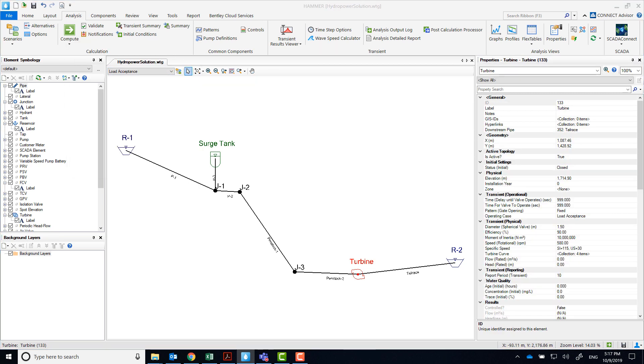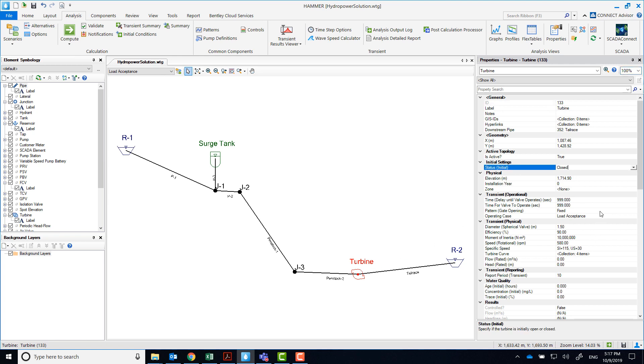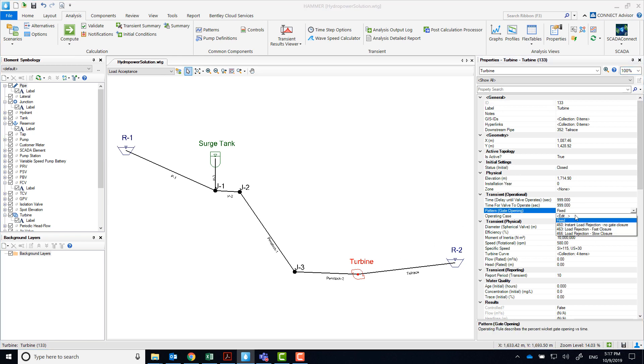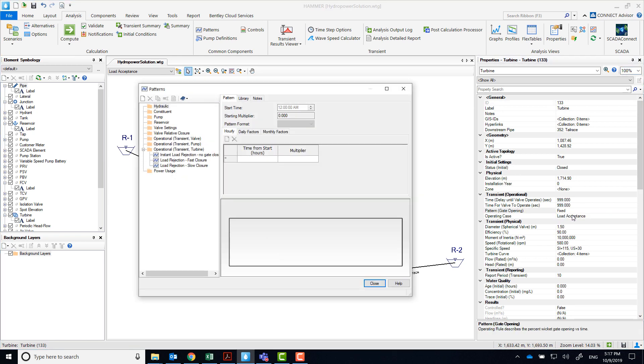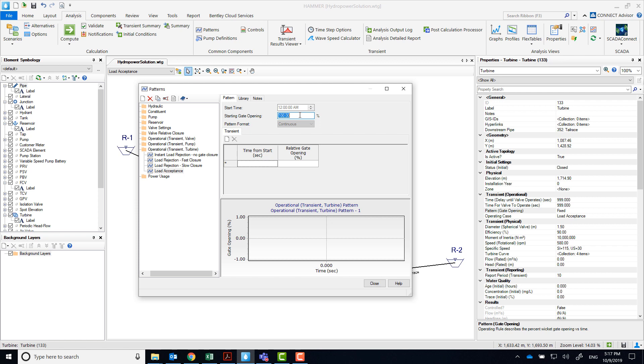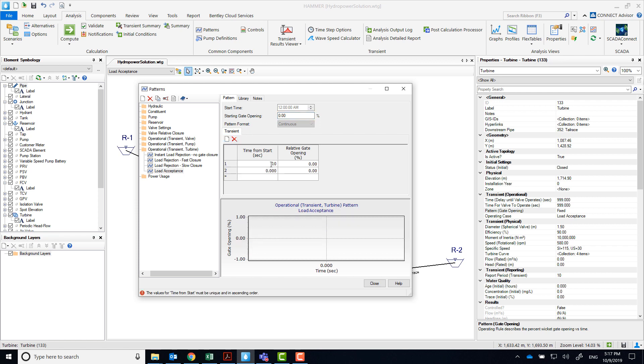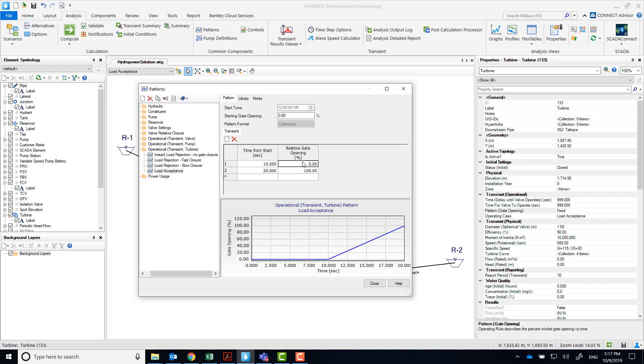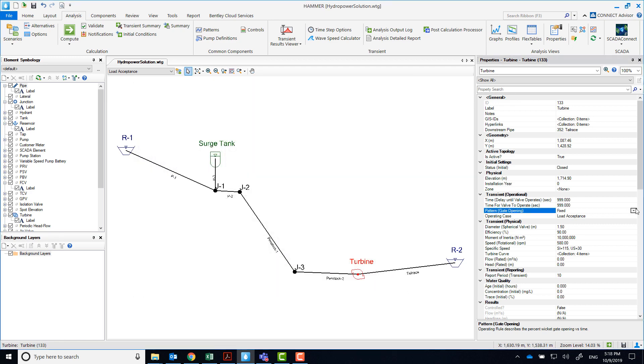Make load acceptance the current scenario, and on the turbine, check that the turbine is initially closed, and create a new pattern. This time, the closed turbine will start to open at 10 seconds, and it will take 10 seconds more to fully open. Select load acceptance as pattern, and also as operating case.